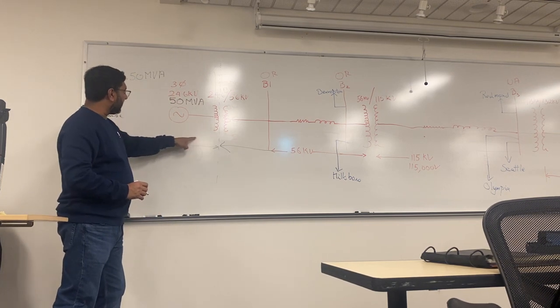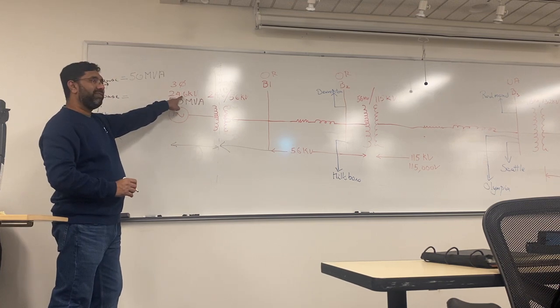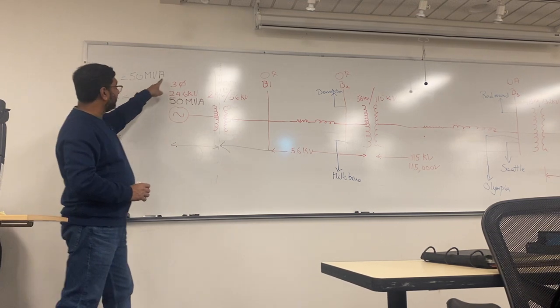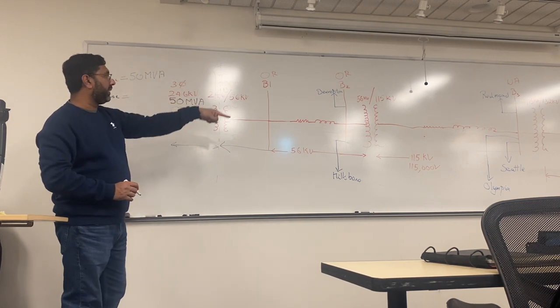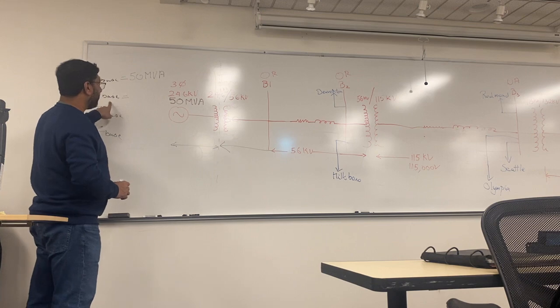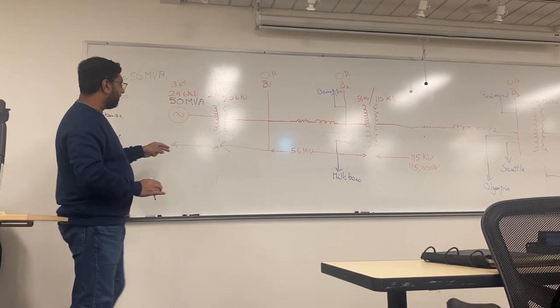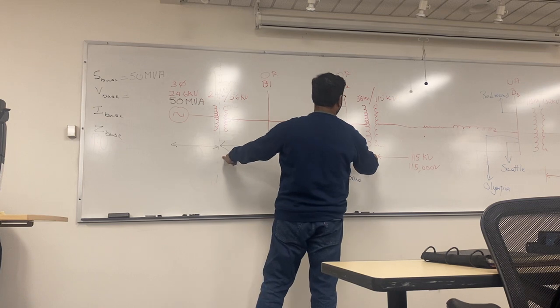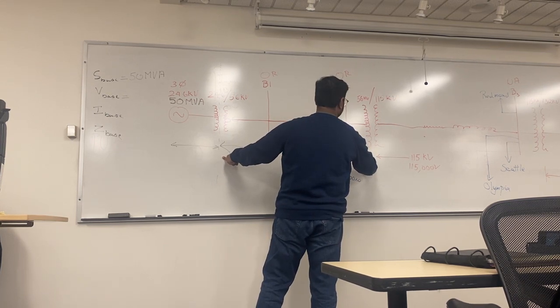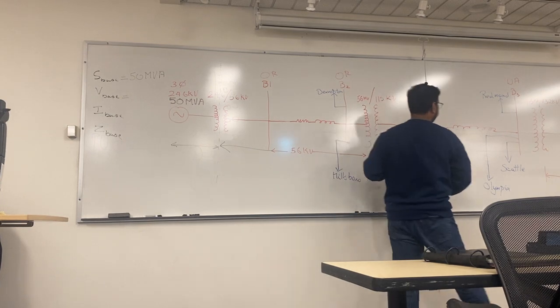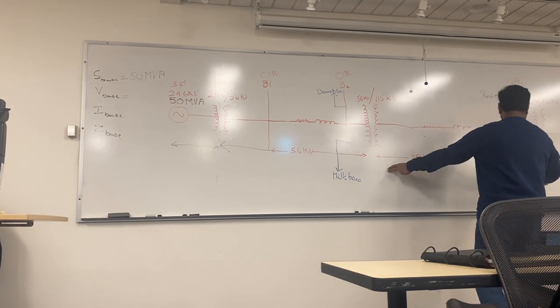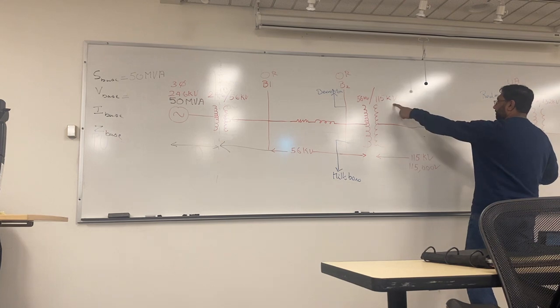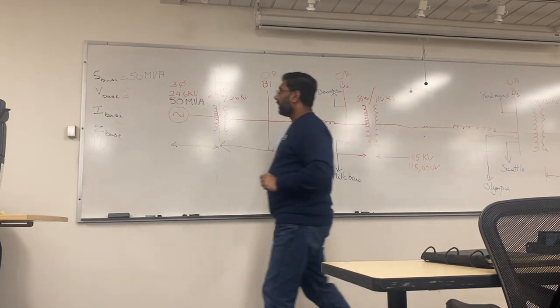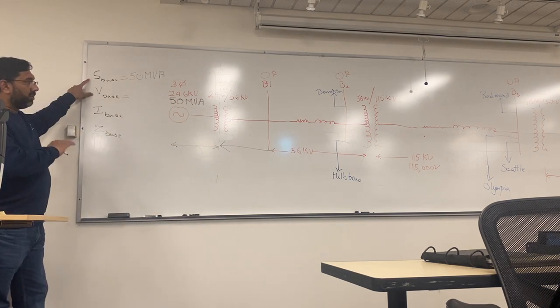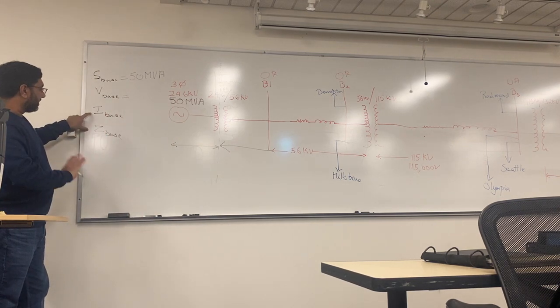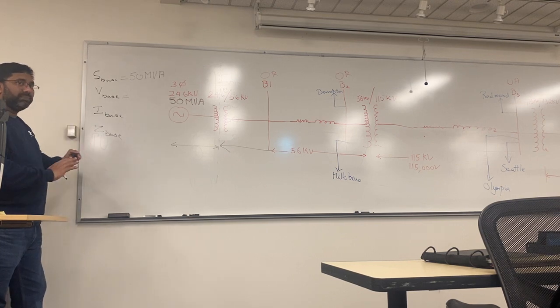Anything happening on this side of the transformer, I'll pick up 24.6 kV as my V base for this section, with 50 MVA throughout the system. The V base I pick depends on where I am. So if I'm discussing something between A and here, my V base would be 56 kV. If I'm discussing something from here to here, my V base would be 115 kV. So you fix these two and then go about figuring out what needs to be done, and that's where all the math comes into play.